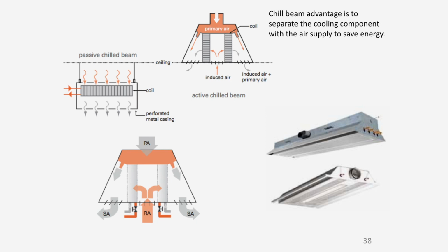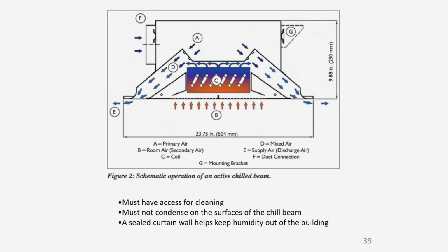What we want is to actually move the air through the chill beam by inducing it, because air is being blown through it, and that's a ventilation principle. Slide 39 shows a little better the complexity of these. They allow us to separate a lot of the thermal demand that's normally handled at the air handling system, so in the chill beam process, it's done locally.